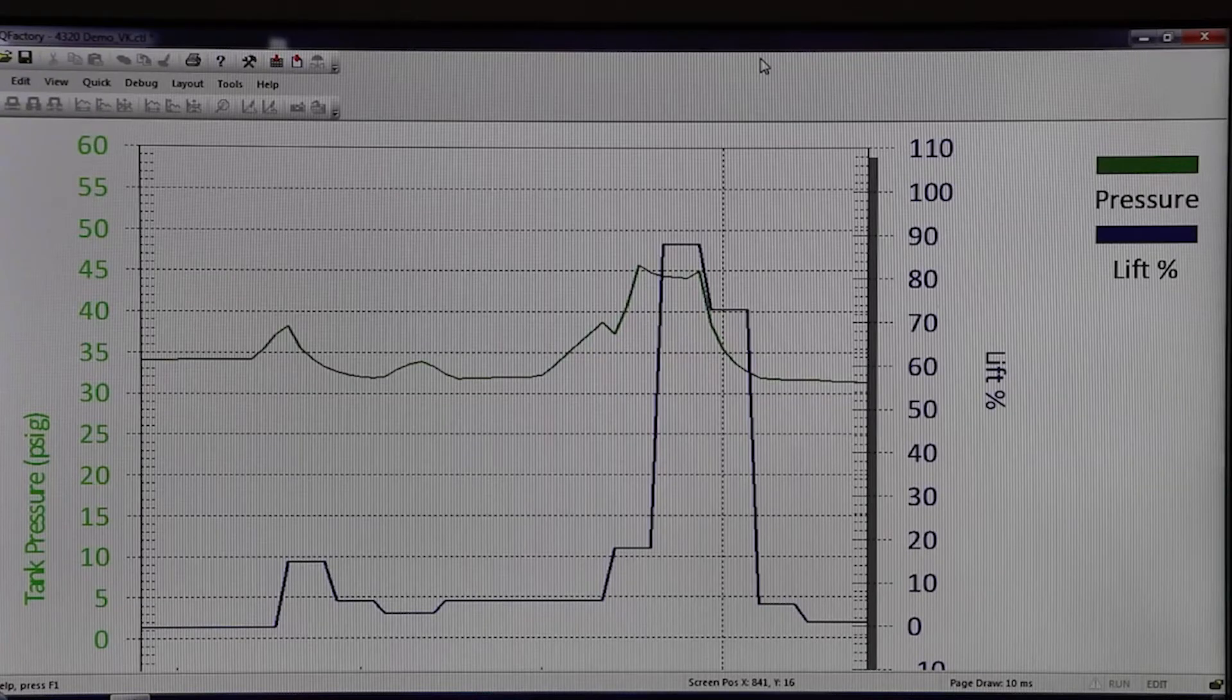As the system pressure increases to the valve's set pressure, the valve immediately pops open, relieving the pressure, and then returns to its closed position after the overpressure event has concluded.